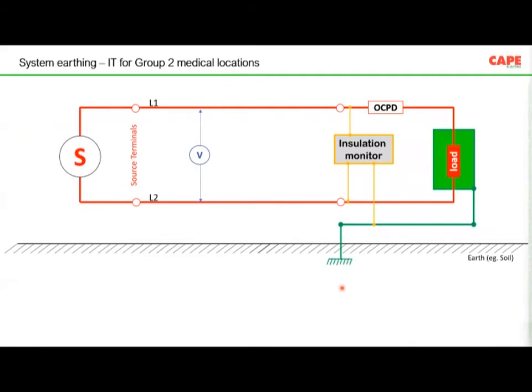Similarly, for group 2 medical location, we can also go for IT, meaning insulated, isolated supply with insulation monitoring devices and a leakage current monitoring system. For example, an IT system means you have the source, probably an isolation transformer, then the secondary side of the isolation transformer, line 1 and line 2, with a voltage of, let us say, 230 volt. These two lines are completely insulated, so these two lines are never connected to earth. Now you have an insulation monitoring device and all this, this entire system, sometimes called a hospital IT panel. A hospital IT panel for group 2 medical location is one of several other requirements. What I wanted to tell you is, don't think that by making a hospital IT panel, you achieve the entire safety.